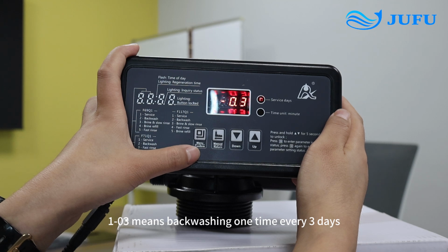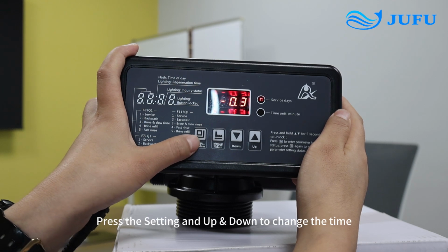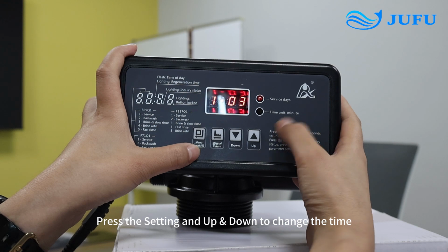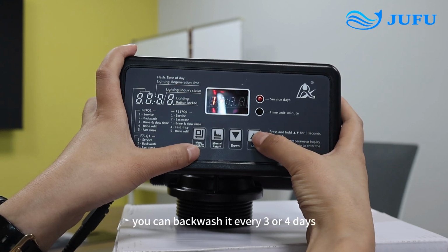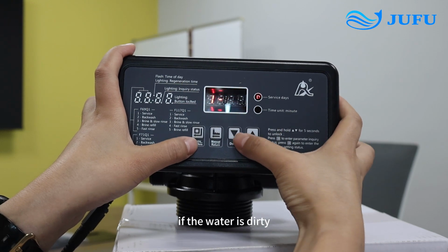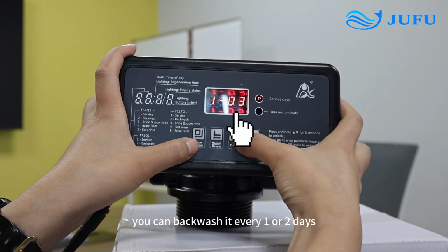103 means backwashing 1 time every 3 days. Press the setting and up and down to change the time. If the water is good, you can backwash it every 3 or 4 days. If the water is dirty, you can backwash it every 1 or 2 days.